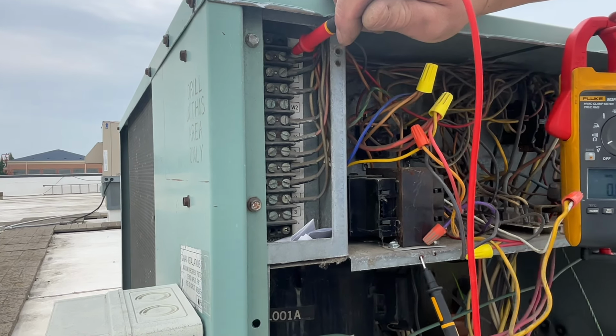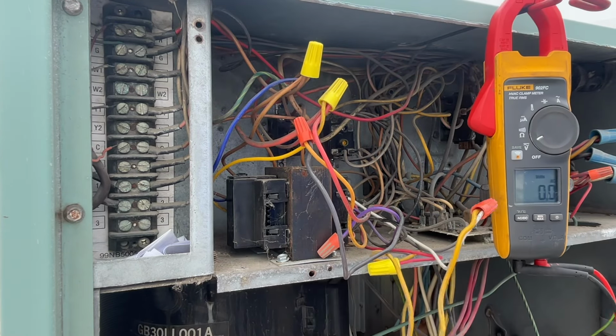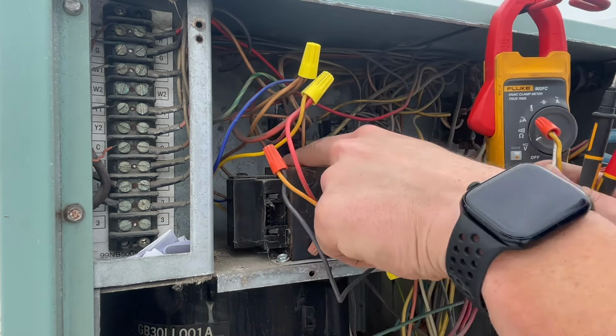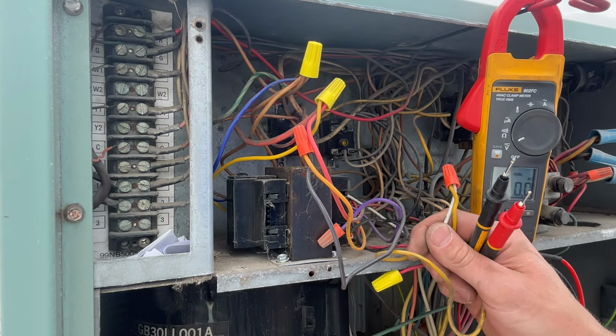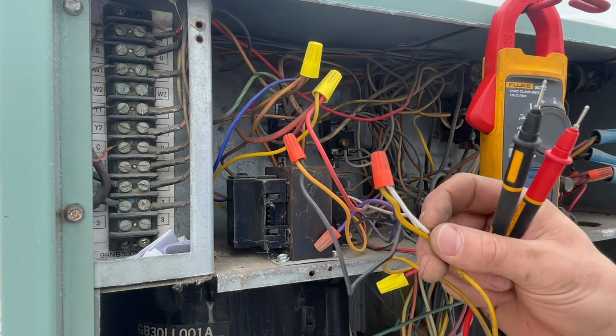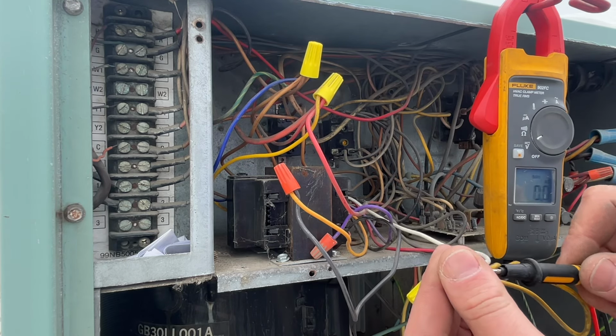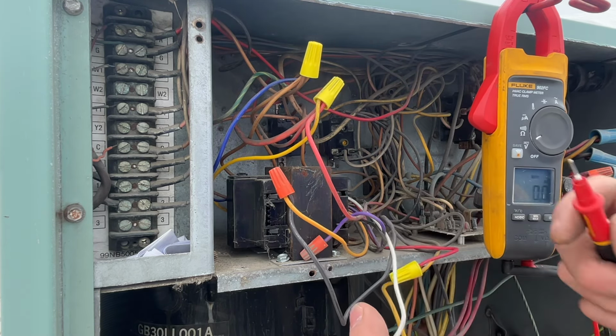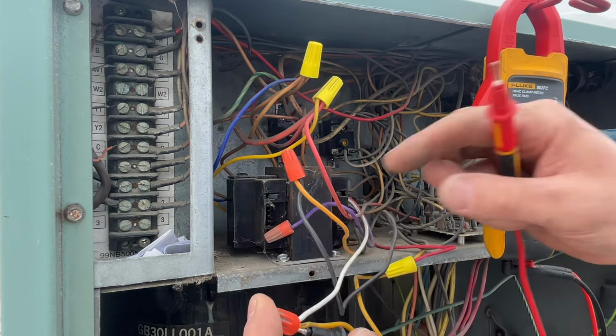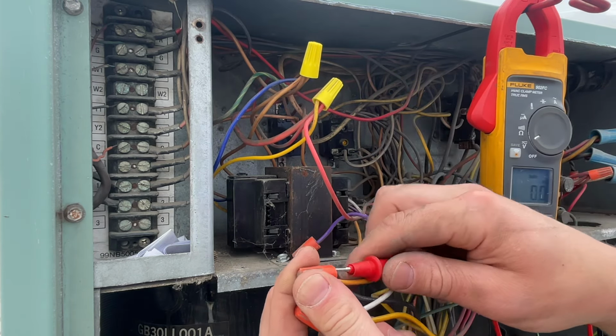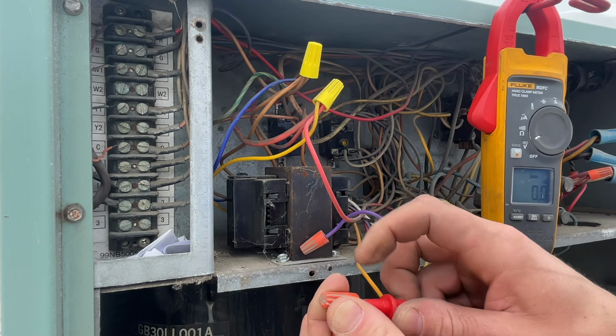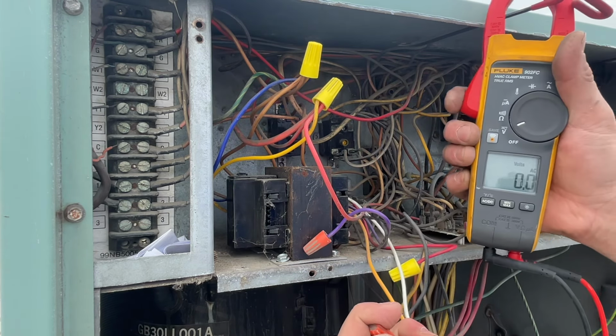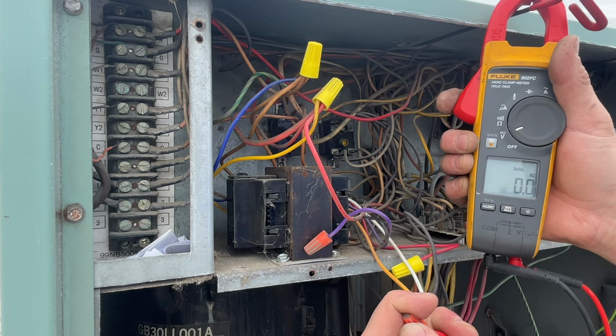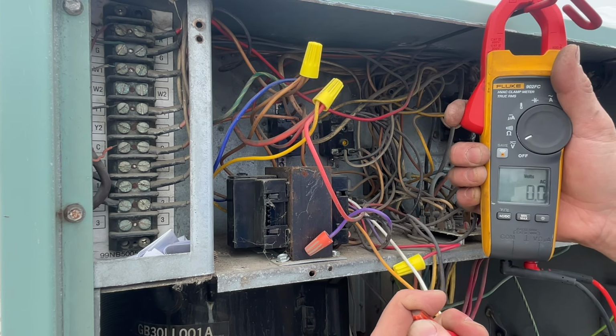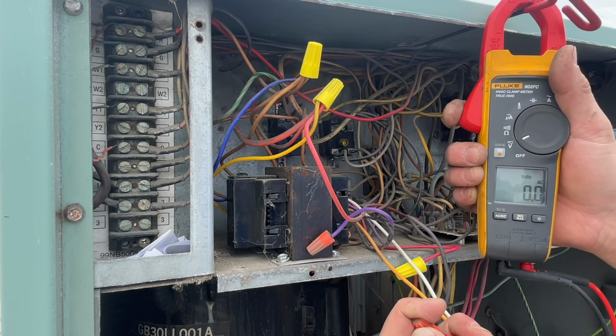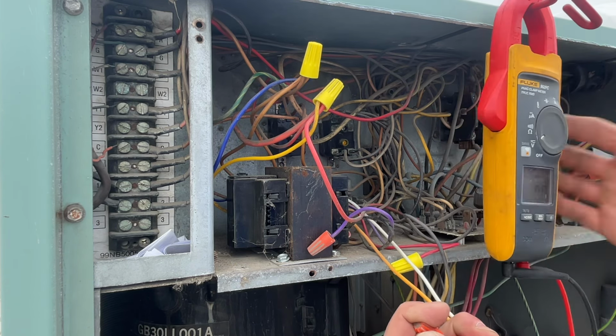And I also checked our inlet power here to our control transformer. And this is a multi-tap. You can set it for 120, 208, 240, or 480 volts. I think 480 would be more popular in the US, but here in Canada, we don't really have that. Not with the equipment in the recent few decades anyways. So we're going across our common, and this is our 240 volt tap. We'll jam our lead in here, and we have nothing, no power. So we have our main inline power, which is fine. We just don't have our control power because we don't have 240 volts from that big shoebox transformer.